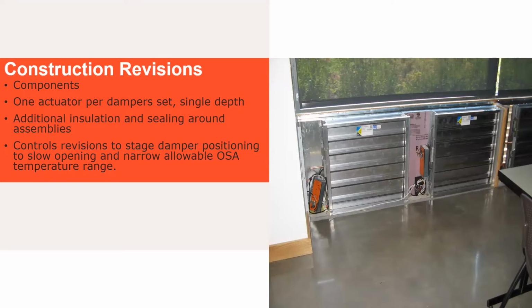With a really good gasket on there, we also upped the torque on our damper actuators and made sure to set those correctly to just prime it, and turn it a little bit more past that. You have to be really careful when setting damper actuators for their zero point, because if you over-torque it, you're going to fail your motor real fast, or potentially damage something. Most likely, depending on how powerful that motor is, you're going to lose that motor in 10,000 cycles instead of 20,000 or 5,000 or 2,000.